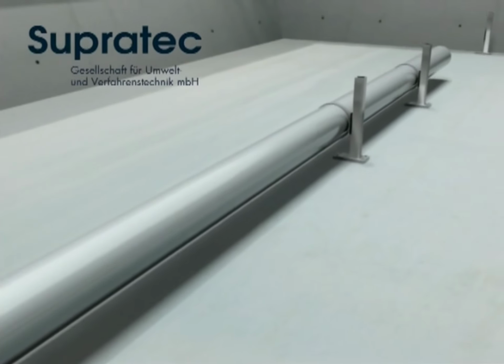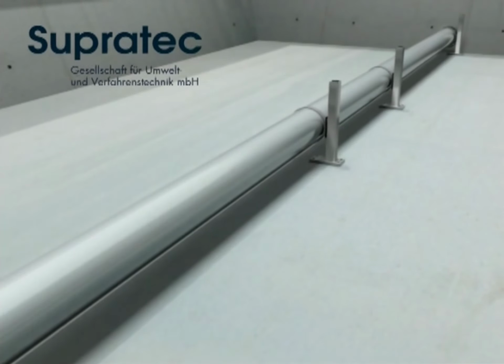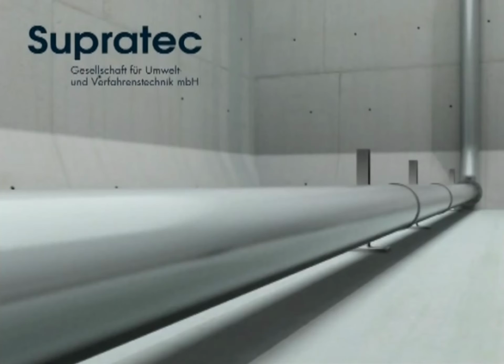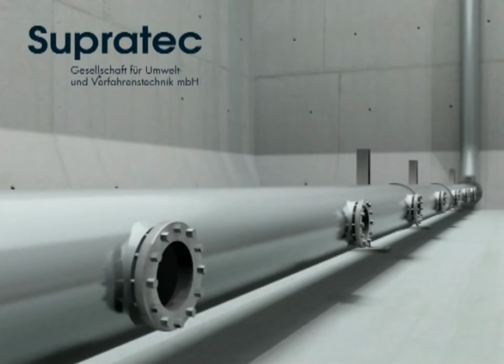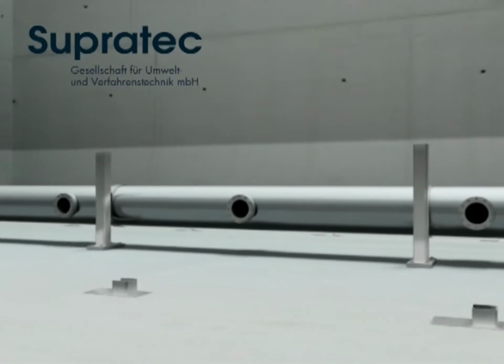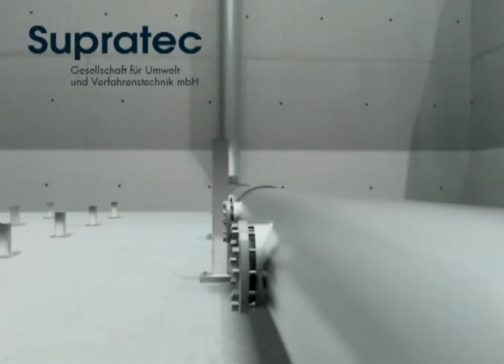Microorganisms in the aeration basin clean wastewater inputs of organic contaminants and nitrogen compounds by means of their metabolism. Large quantities of oxygen are needed for this. For this reason, compressed air is introduced into the aeration basin in the form of fine bubbles. The oxygen content dissolves into the wastewater and is available for use by the microorganisms.